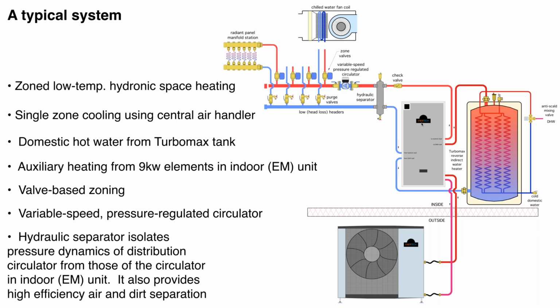Now, again, the indoor unit is set up so that it can automatically go to a TurboMax indirect water heater. And we talked about the importance over the last several webinars. We talked about the importance of low water temperatures. And when it goes to domestic water heating, obviously we need water temperatures, I would say as a minimum in the range of 110 to maybe 120 degrees Fahrenheit. So the unit is going to operate probably at a slightly higher temperature during the domestic water load. And that's why we want to have a lot of surface area inside that tank.